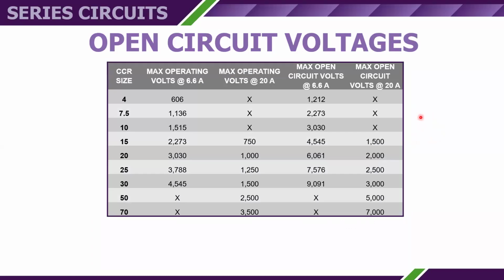Now, these are the typical operating voltages at 6.6 amps. This is what the open circuit voltage would be on the regulator as the open circuit occurs. A fully loaded 30 kW constant current regulator will operate at 4,545 volts across the output terminals. This is your nominal normal voltage. That's why our cables are rated at 5,000 volts. But if you open circuit that regulator, it will jack the voltage up to a little over 9,000 volts, trying to maintain the 6.6 amps. It'll raise that voltage for 2 seconds. If within 2 seconds it does not complete the circuit and get current flowing again, it will shut itself down.